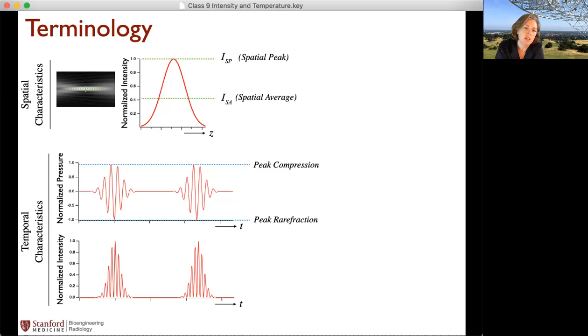Of course, if we talk about the intensity, to get there we take our pressure, square it, and divide by the acoustic impedance. We have our temporal peak intensity. We have our temporal average intensity. So if you have multiple pulses, then you might define the temporal average over the whole time period. And of course, there's also a pulse average, which is just the average over the period of the pulse itself.